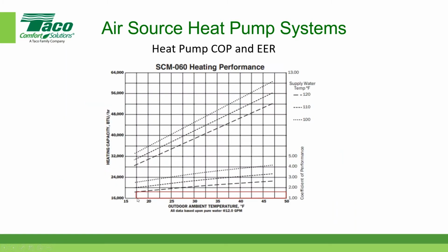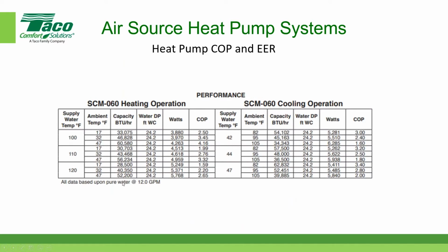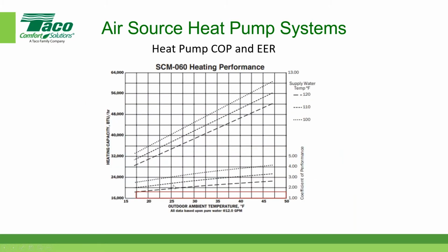And so if you look on the chart, again, this is 15, 20, so it's about 17 and a half. So it's about 17 degrees. And where it hits the bottom line here, that's the 120 degrees. So it produces 120 degree water with a COP. So there's 1.0, and then halfway up would be 1.5. So it's about 1.6. And I think that's, let's go back to that previous. And yeah, it's 1.59. So you can see that as the ambient temperature begins to drop off, the capacity of these air source heat pumps drops off, and also the COP begins to drop off.